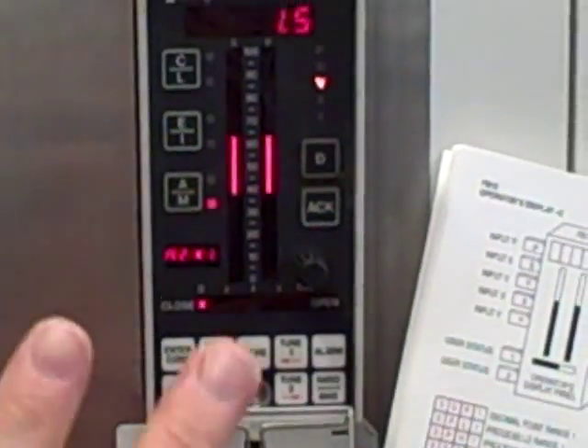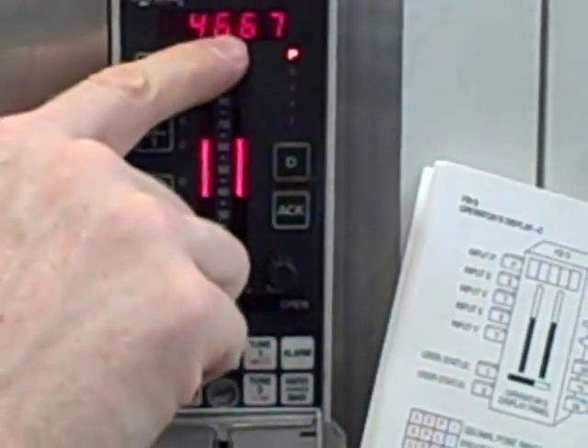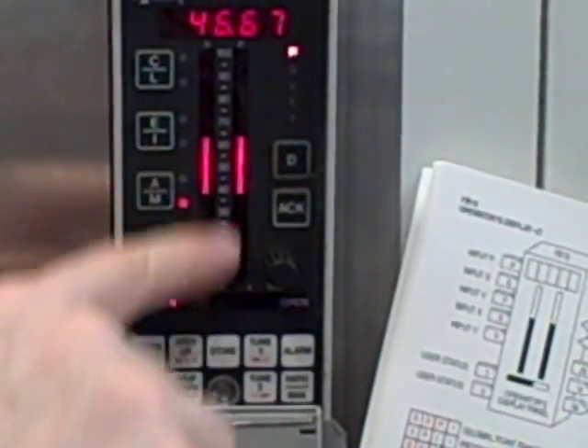So now I've set my low and high process range values to 50 and 150 respectively. I'm done with that. I can hit my exit button, get out of the configuration, and now when I go to process display, it bottoms out at 50.